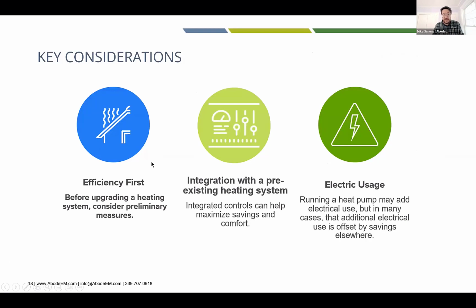So just some key considerations: before upgrading a heating system, make sure the house is as buttoned up as possible. And if that's not implemented, size the heat pump system for the changes that will happen while you're in ownership of the home. So if you're planning on replacing all your windows in the next 2 or 3 years, I would size the heat pump system to reflect that if you have an existing heating system in place. There's no reason to be oversizing the heat pump system for the house as is versus where you're planning on getting the house to be.